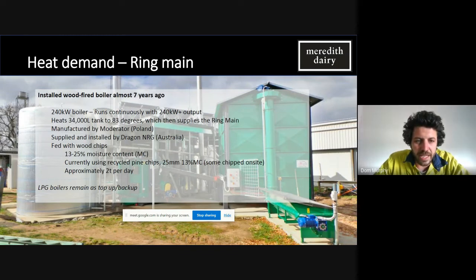What that does is heats two tanks for us, 34,000 litre buffer tanks. And the idea behind that is that we have peaks in our demand, and then we have a very long downtime overnight. By having those buffer tanks, it allows us to have a smaller boiler operating at a pretty consistent temperature, and it's a thermal battery, so it allows us to build up that heat over those downtimes. The boiler was supplied by a Polish manufacturer and installed by a company called Dragon Energy in Australia, and we feed it with wood chips.